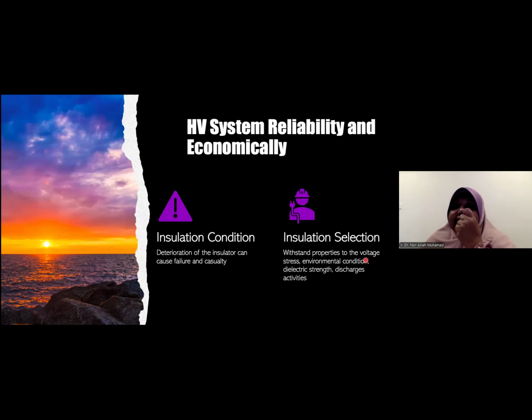So insulation selection is very important. The withstand property of the voltage stress, environmental condition, dielectric strength, and also discharge activity are the factors that we must consider in order to select the insulation material.